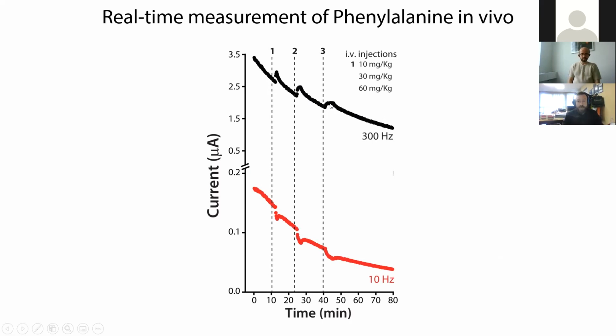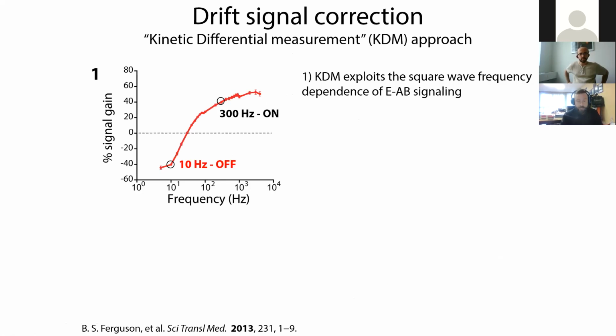So it's clear that the sensor can respond to the target, but this drift observed at the 2 different frequencies does not allow us to convert the signal into a concentration of phenylalanine. So this signal drift seems to affect the performance of the sensor. To solve this problem and to correct the signal, we apply an approach called kinetic differential measurement. This is an engineering approach, and it's based on 2 different assumptions.